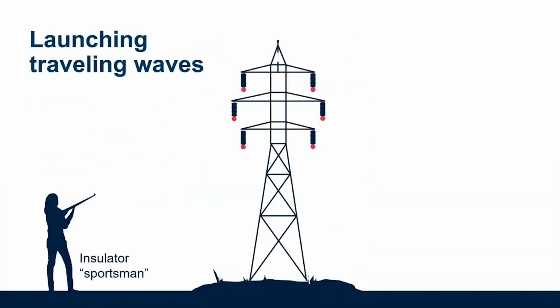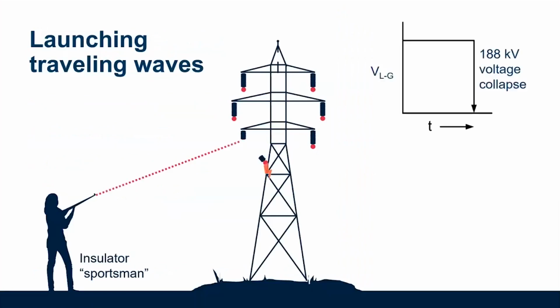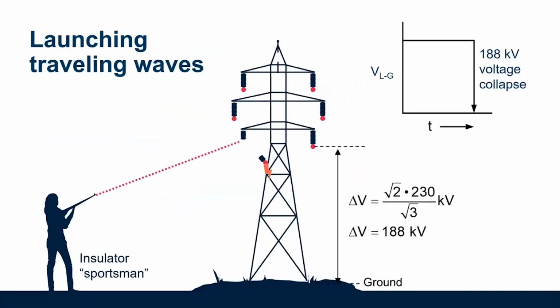Okay, so when a fault occurs, we're going to have a large step change in voltage. And if voltage is at our peak, we're going to see it go from the peak, so √2 times the phase voltage over √3. So this equation right here is going to be able to tell you what your change in voltage is going to be. So with this large step change in voltage, we get a traveling wave that is launched from the fault point to the terminals. So we're going to get both current and voltage traveling waves launched from the fault point.